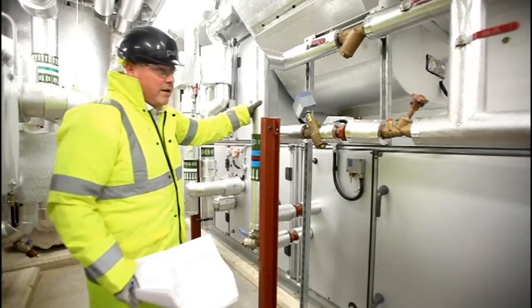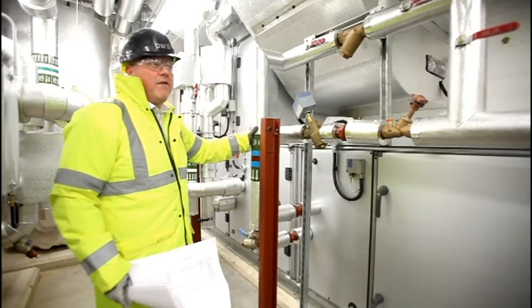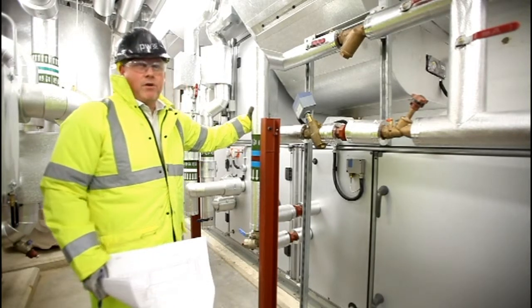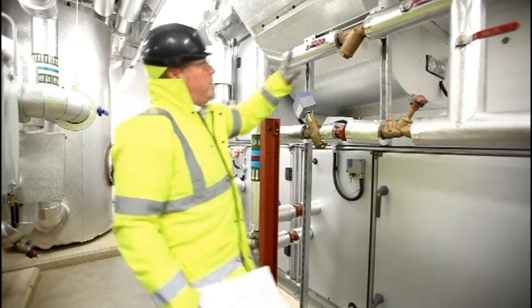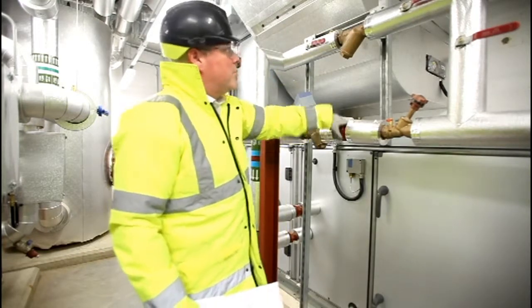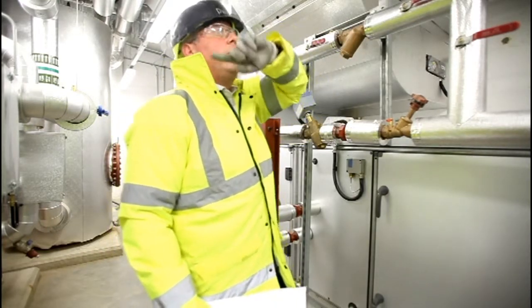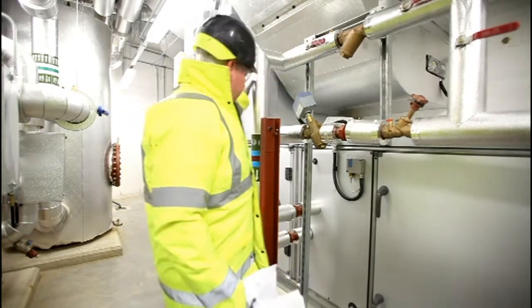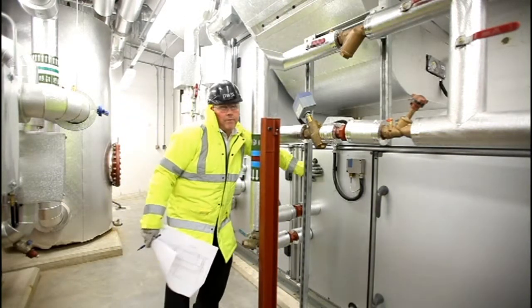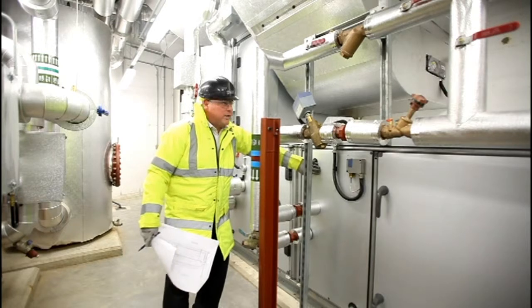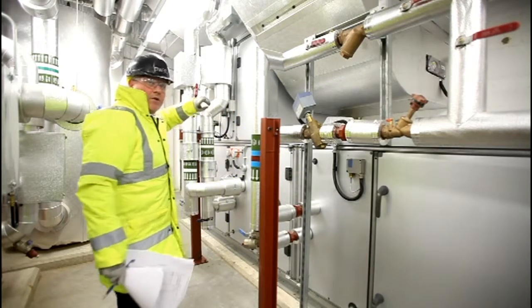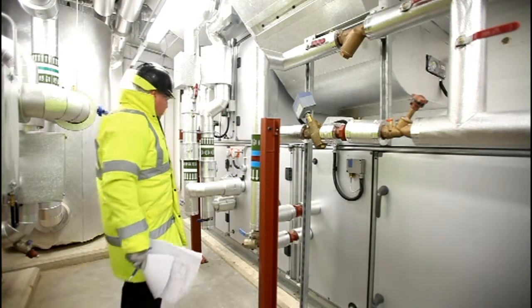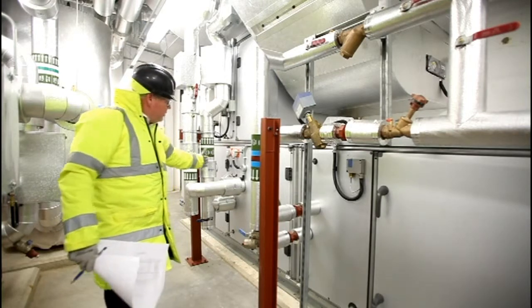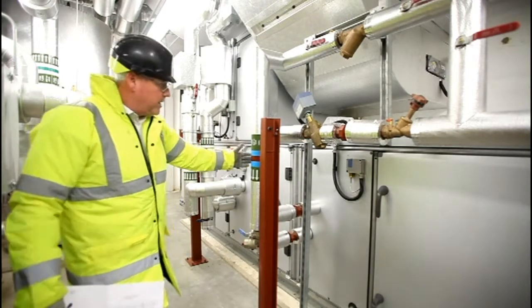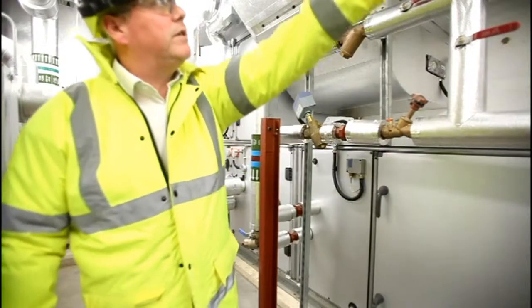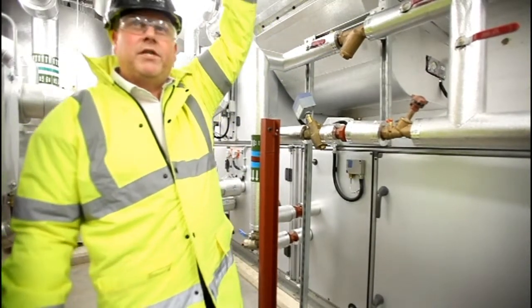What we have here is an air handling unit. This is air handling unit number 5, and this does gallery number 5. So we have heating, comes through from the boilers, through the pumps, through the system, into a large coil which is inside the air handling unit. We take fresh air from outside the building. It comes through the process, blows through the unit, passing the heating coil, out of the unit, and distributes up into the gallery spaces above.